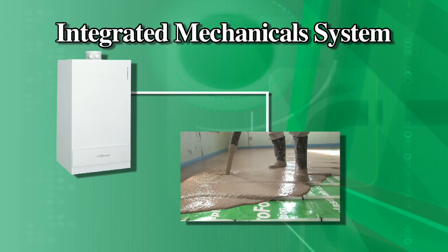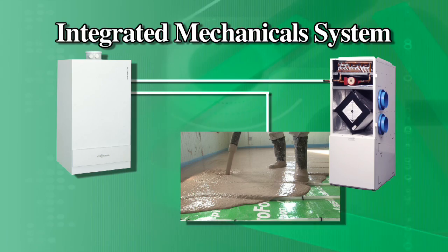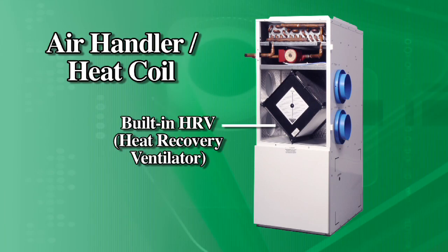So the opportunity with using the boiler as an integrated mechanical system is that it heats hot water and sends it either to the radiant floor distribution system or to a fan coil that converts the heat into an airstream. The equipment we've specified in this house is basically an integrated mechanical system, because it incorporates ventilation and heat recovery into the air handling system. We're able to use one fan to do a bunch of different jobs, and we could easily add air conditioning to that.